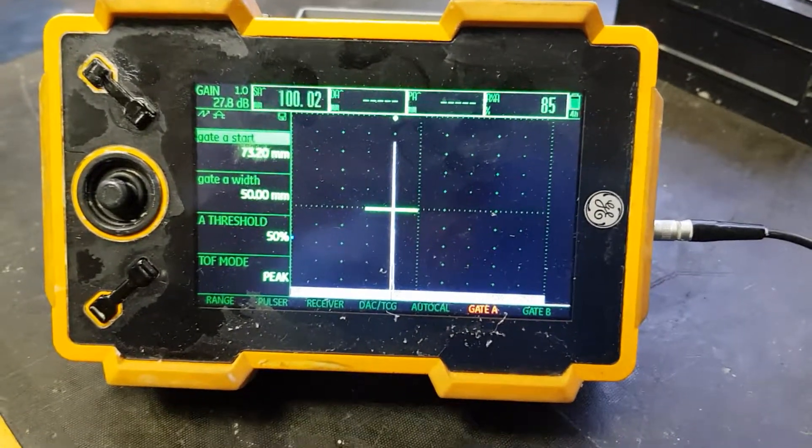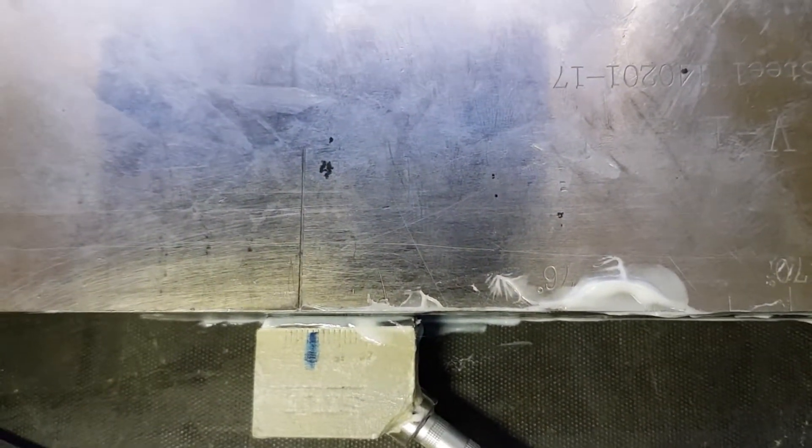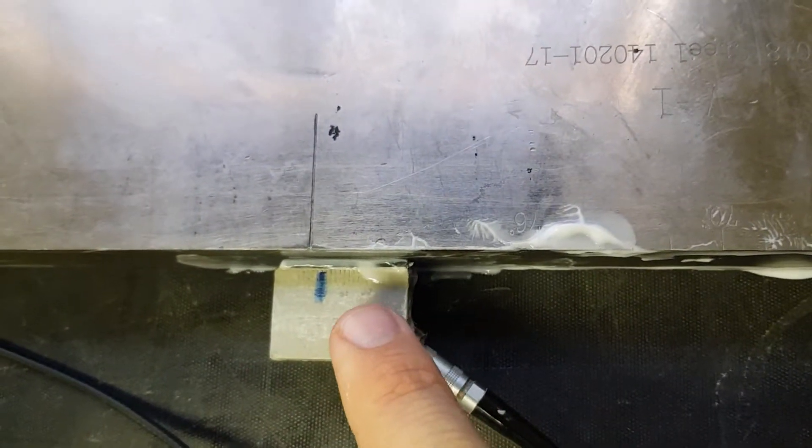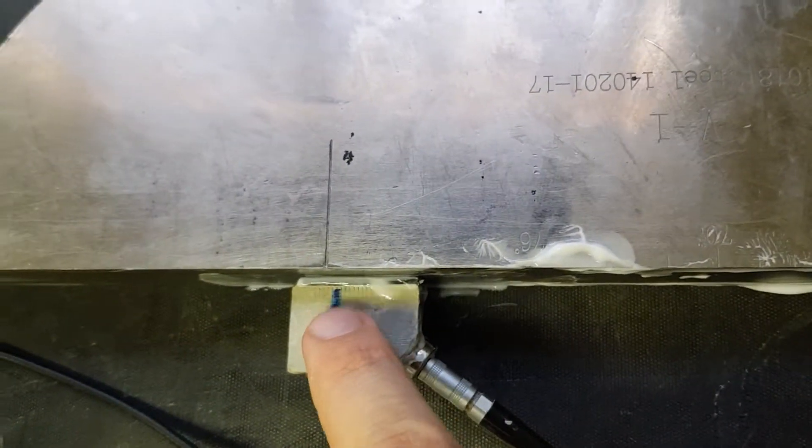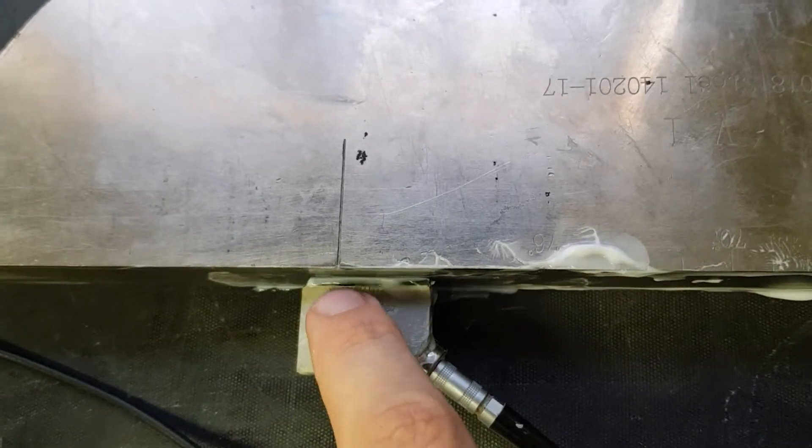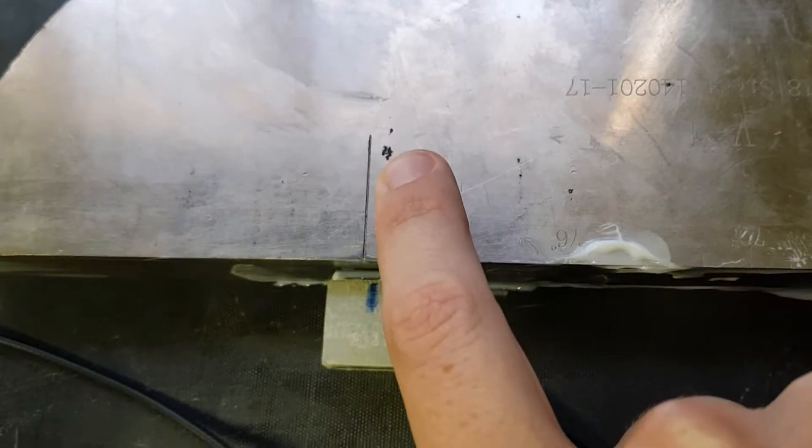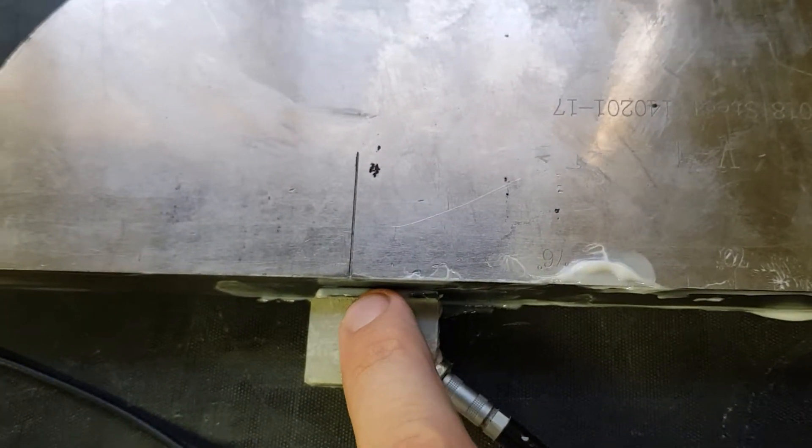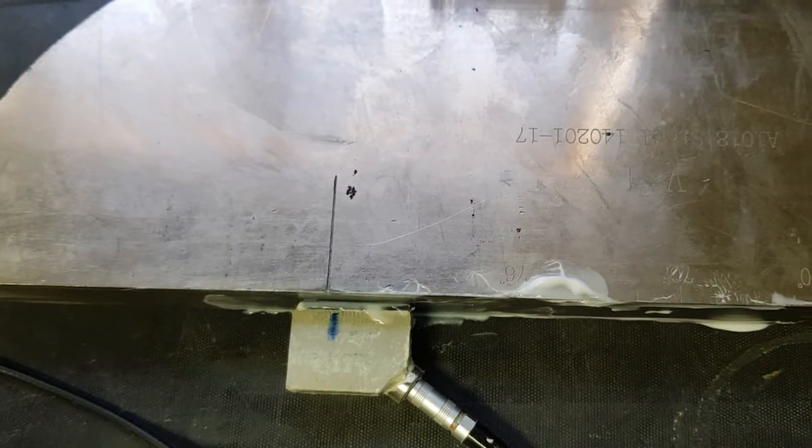The next step is to mark your probe index point. You can see the mark here is slightly incorrect. I would just stick some more masking tape on the probe, take a marker pen, and mark where this long line of the V1 block lines up with the probe. Very important.